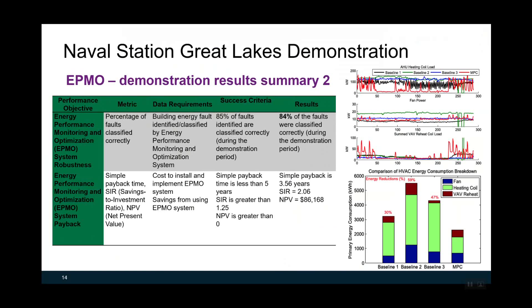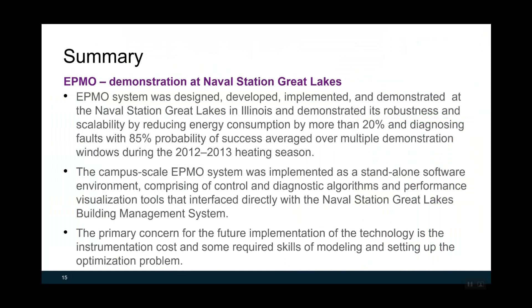In summary, the EPMO system was designed, developed, implemented, and demonstrated at Naval Station Great Lakes. It demonstrated its robustness and scalability by reducing energy consumption by more than 20%, with 85% probability of success averaged over multiple demonstration windows during the 2012-2013 heating season. The campus-scaled EPMO system was implemented as a standalone software environment comprising control and diagnostic algorithms and performance visualization tools that interfaced directly with the existing building management system. The primary concern for future implementation is instrumentation cost and the required skill for modeling and optimization problem setup.